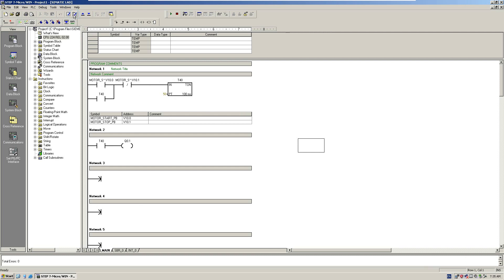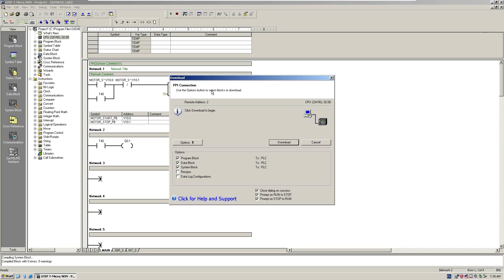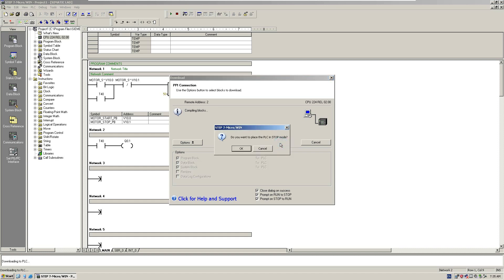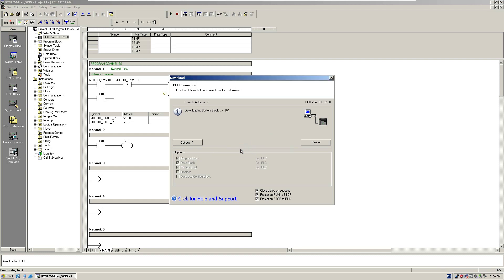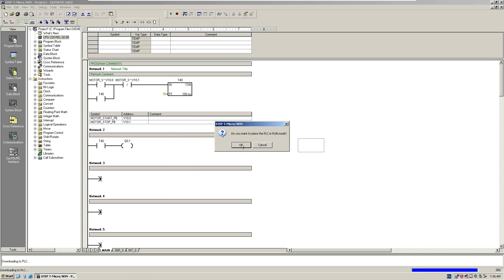Once we finish the program, we hit compile. Error is zero. Then we try to download to the controller. We hit download. It shows: do you want to place the CPU PLC in stop mode? That's because for the 200 controller, once we download, the controller needs to be stopped. Once all the program is downloaded, the CPU will start, but during the download the CPU has to be stopped.